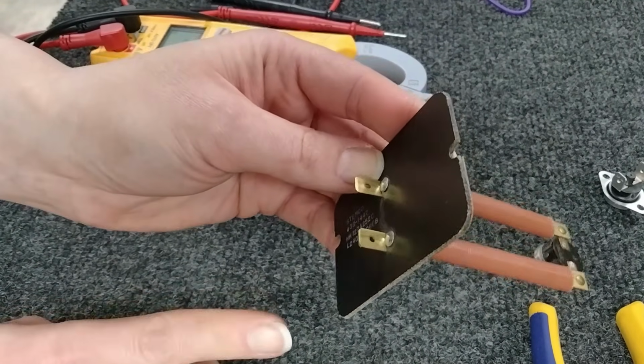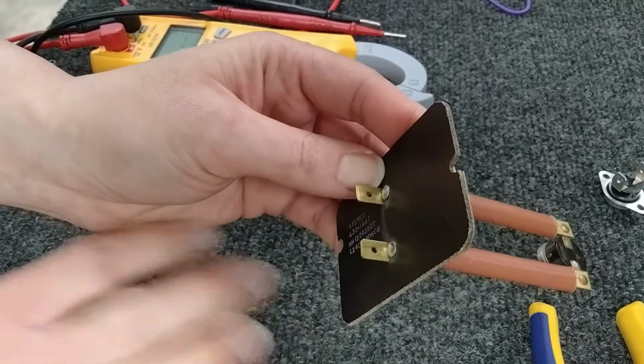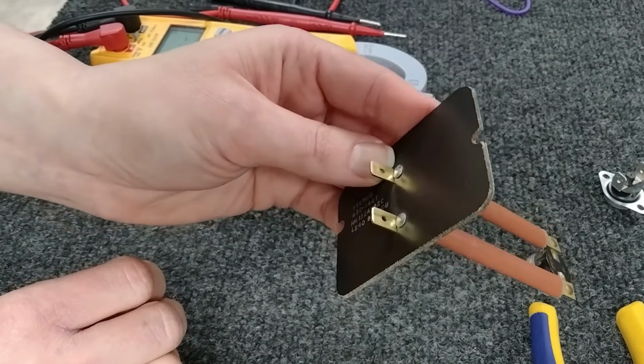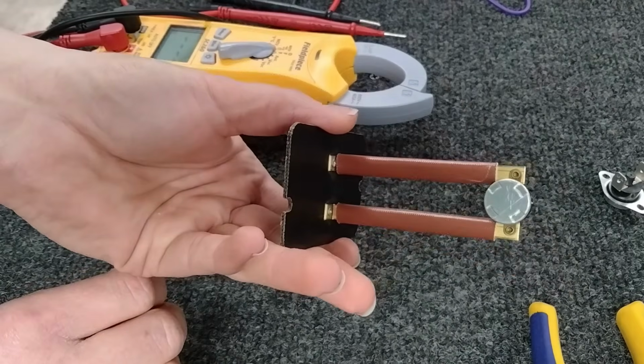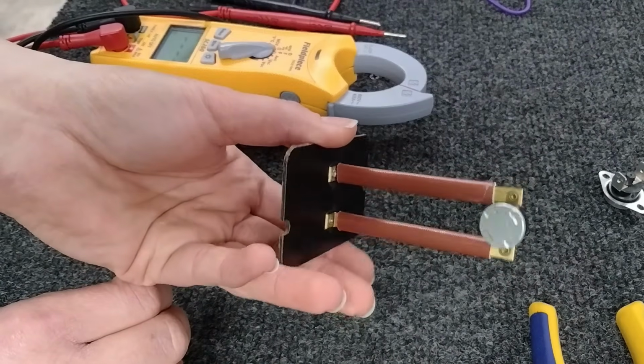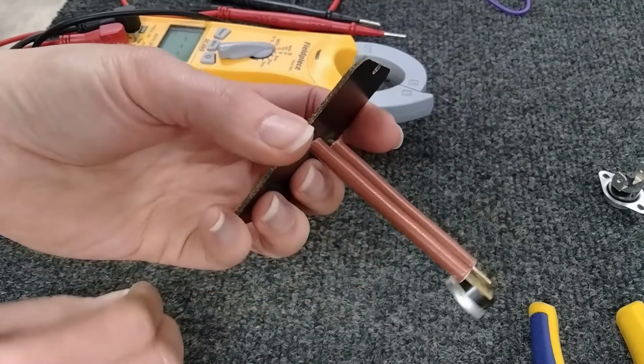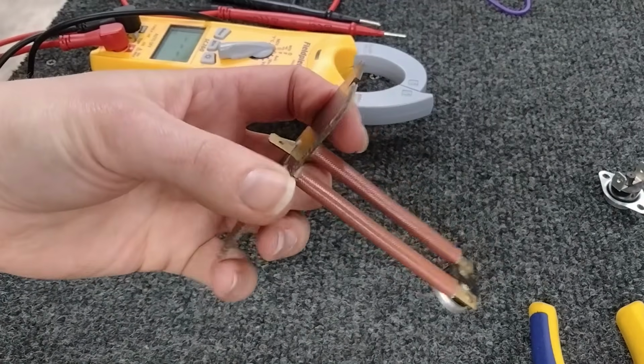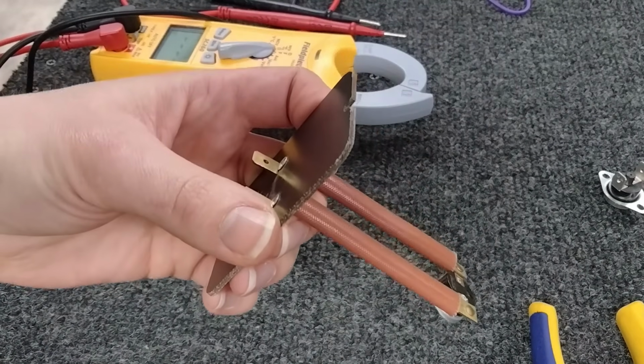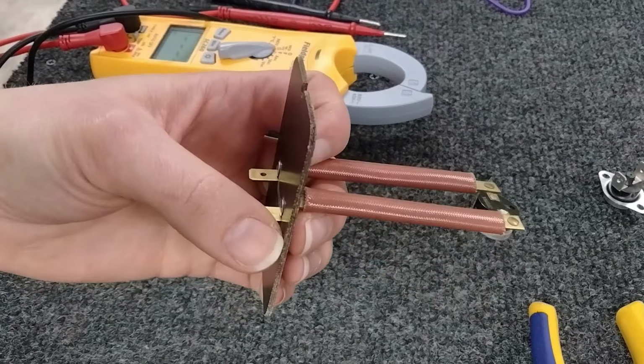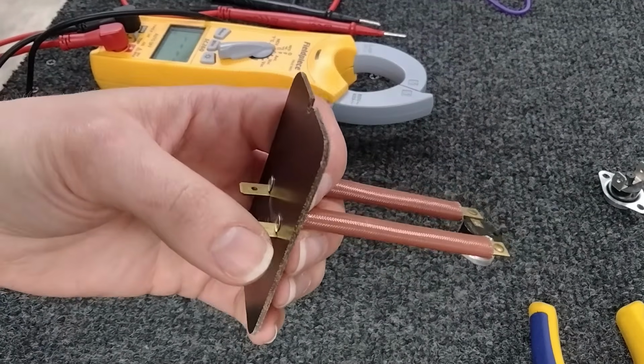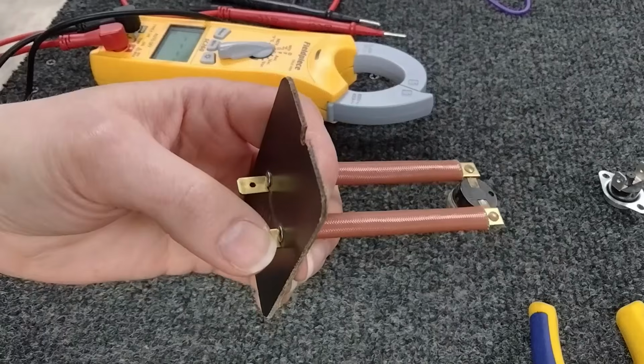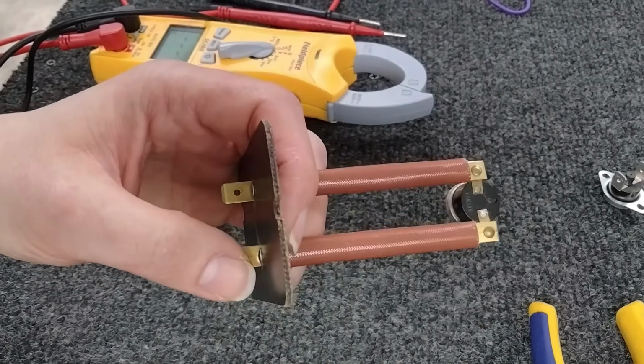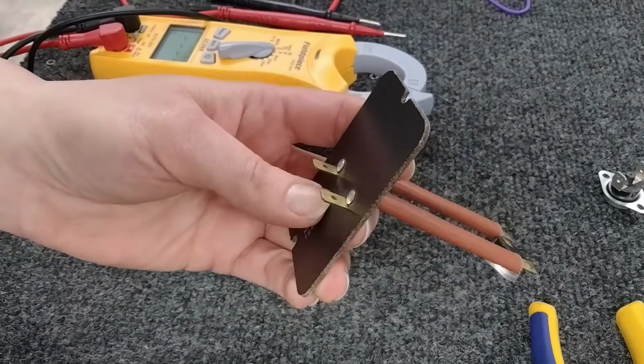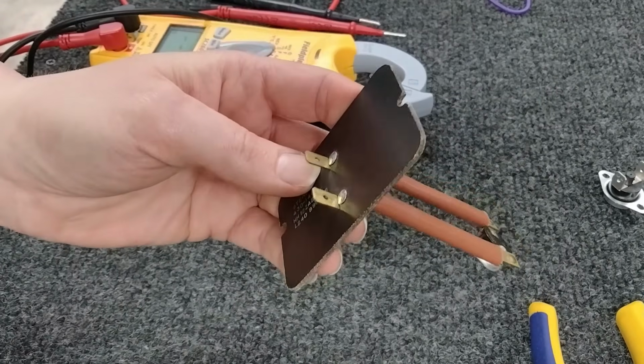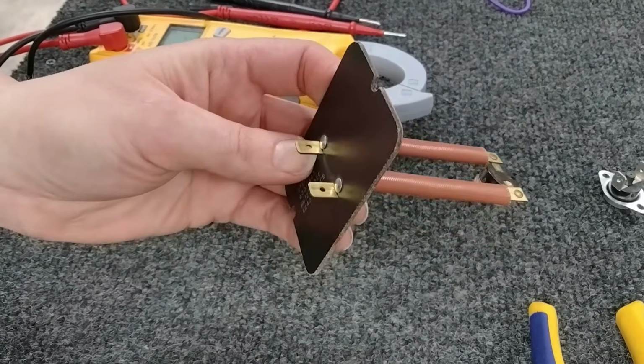It's important that you don't. It's a safety hazard. It's a fire hazard. So don't burn your house down. If your high limit switch is bad, a pretty good indicator is, even when you reset the power on your unit and let it sit for a little while, if you cut it back on and immediately both your main blower motor and your inducer motor come on, this is usually the culprit. Also, the board will kind of let you know, hey, bad high limit switch.